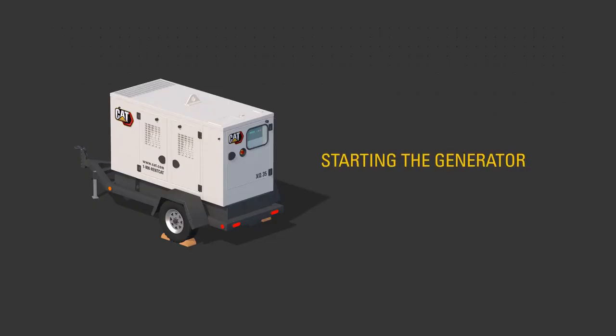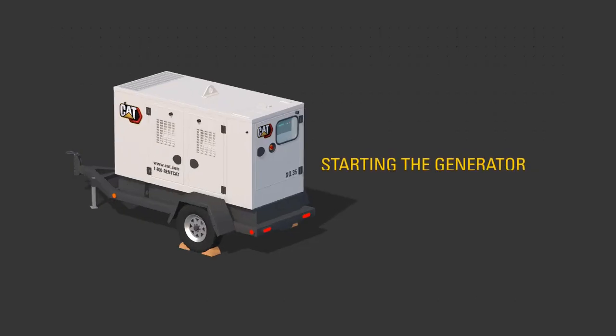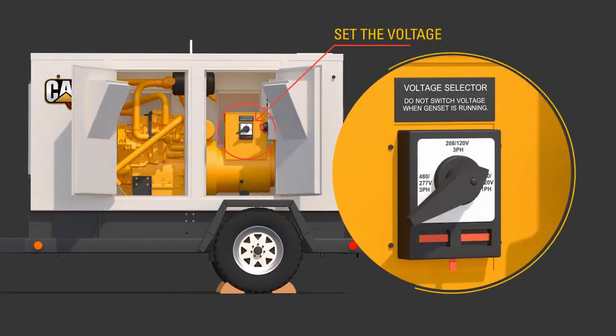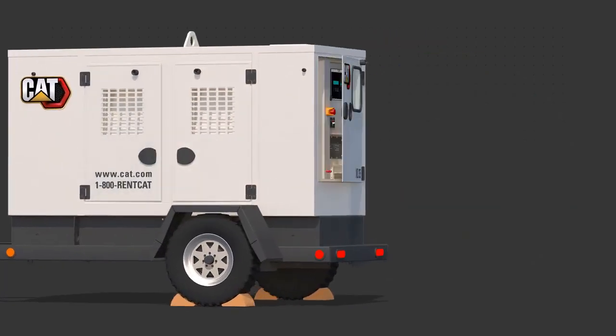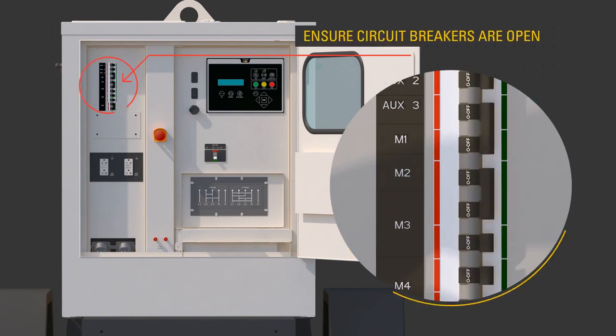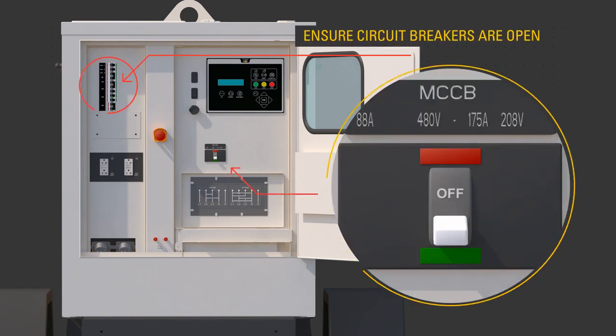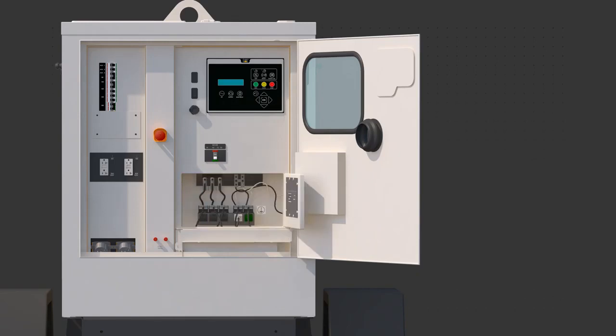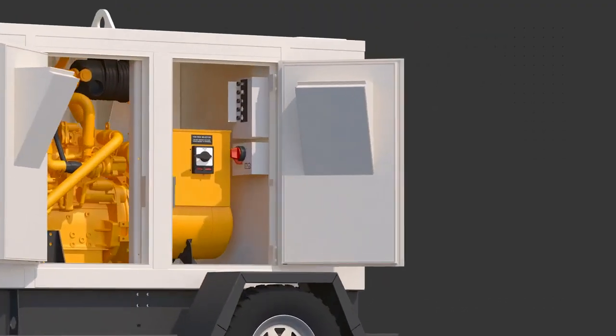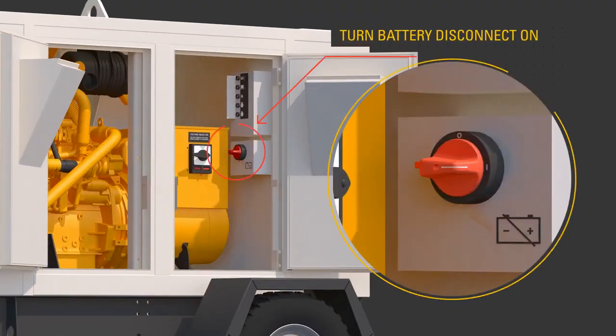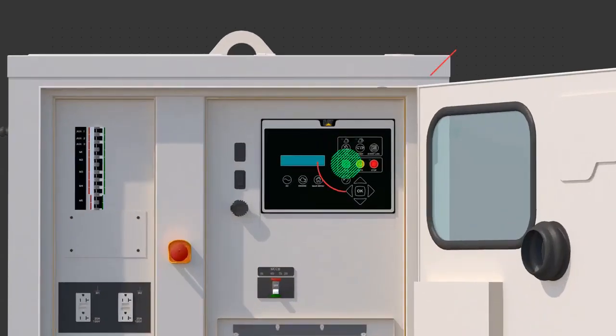To start the generator, select the desired voltage using the voltage selector switch. Ensure the circuit breakers are open, off. Connect required cables to the bus bar only while the product has no power source or is in a zero energy state and not running. Turn the battery disconnect to the on position. Press the run button. The generator set controller, or EMCP, confirms the engine is running and there are no faults.